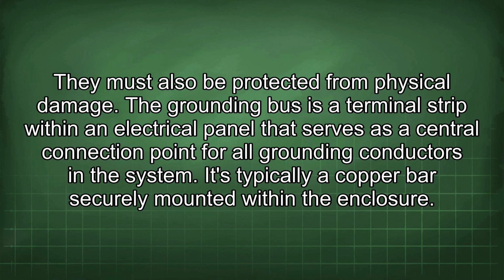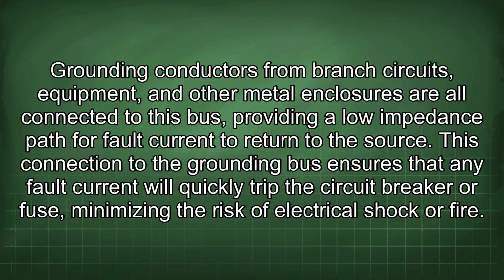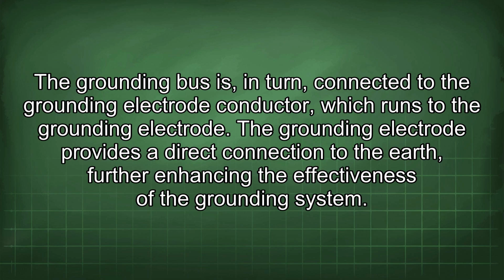The grounding bus is a terminal strip within an electrical panel that serves as a central connection point for all grounding conductors in the system. It's typically a copper bar securely mounted within the enclosure. Grounding conductors from branch circuits, equipment, and other metal enclosures are all connected to this bus, providing a low impedance path for fault current to return to the source. This connection to the grounding bus ensures that any fault current will quickly trip the circuit breaker or fuse, minimizing the risk of electrical shock or fire. The grounding bus is, in turn, connected to the grounding electrode conductor, which runs to the grounding electrode. The grounding electrode provides a direct connection to the earth, further enhancing the effectiveness of the grounding system.